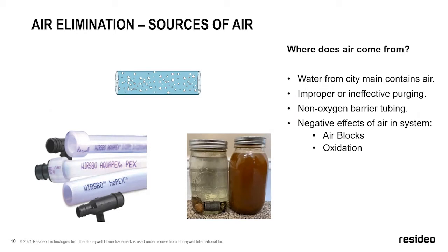If you don't have an oxygen barrier, you are having oxygen permeation take place inside that plastic, which is constantly introducing oxygen molecules into the system. Those oxygen molecules are going to produce rust on any kind of ferrous metal. You'll have iron oxide being created, all kinds of issues. And I've got an example here. There are third-party manufacturers that make boiler chemical inhibitors that help prevent some of this. Fernox is one of those brands. We don't have any ties to them. It's just a brand I see a lot.